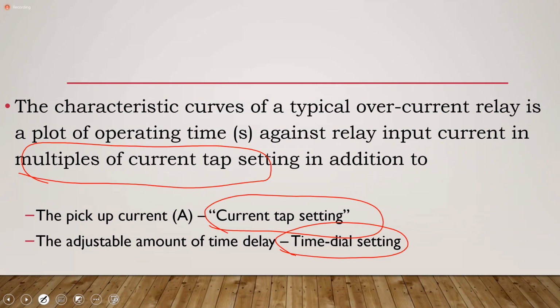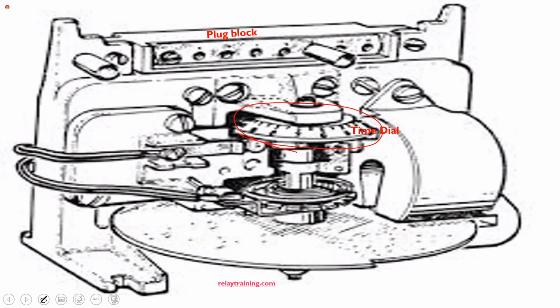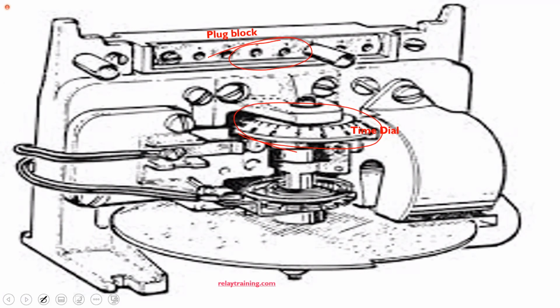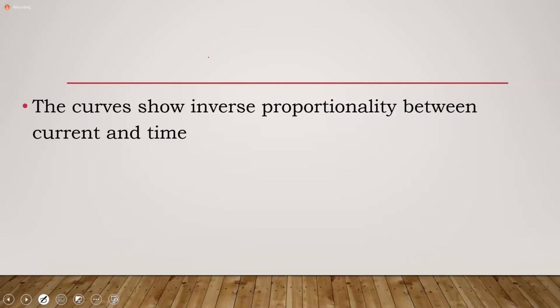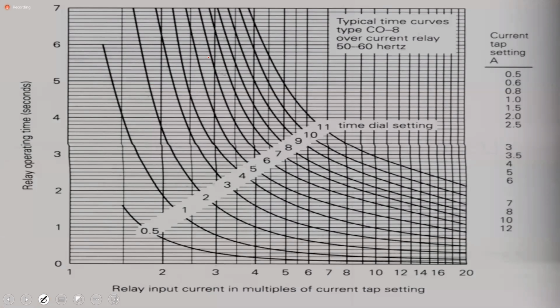Going back to the figure, I set the time dial and I set the plug. Those are the two settings that I would have for my relay. We're not going into relay setting now. That's not on this syllabus. What I want to highlight are the curves. Remember we said you have the time dial setting, and everybody has this figure, right? I did send it, so you should have it. So you have the time dial setting. Note this one, the CO8. This is just the name of the relay. So the CO8 relay starts from 0.5 and then 1 through to 11.